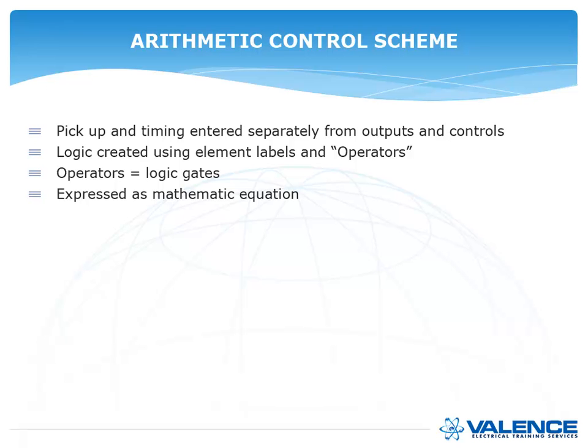The arithmetic scheme uses pickup and timing, is entered separately from the outputs and controls, just like the last couple of schemes. The logic is created using element labels and operators. So those are all those little lovely letters and numbers in that chart that I showed you earlier. And the operators are logic gates, and it's expressed as a mathematical equation.